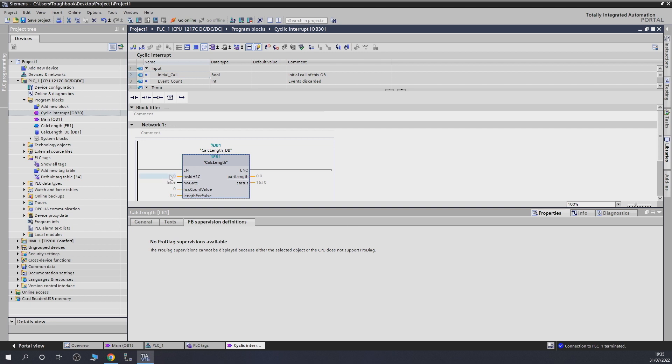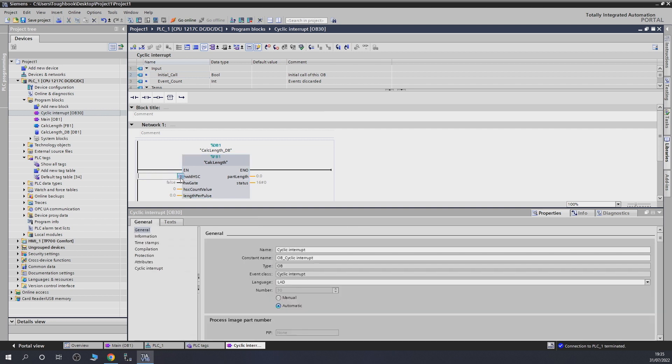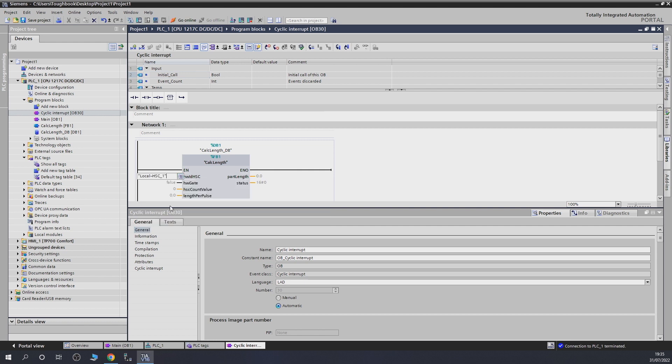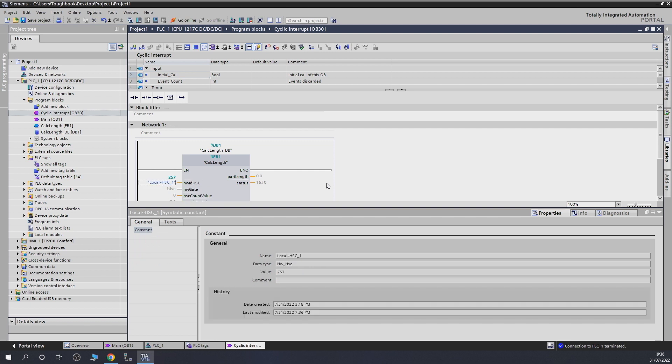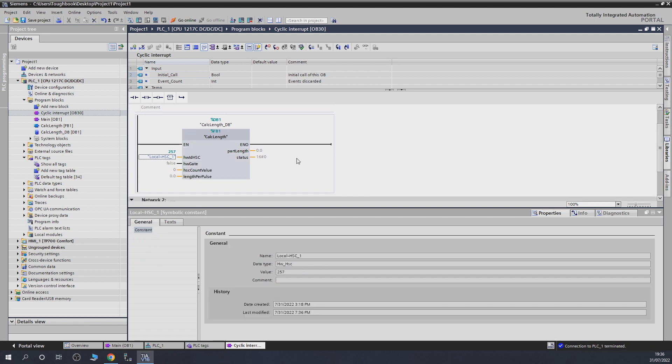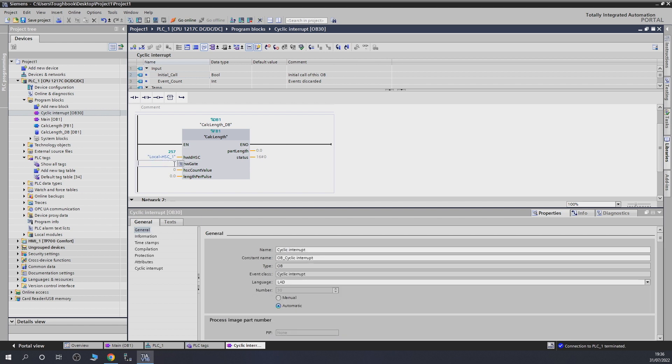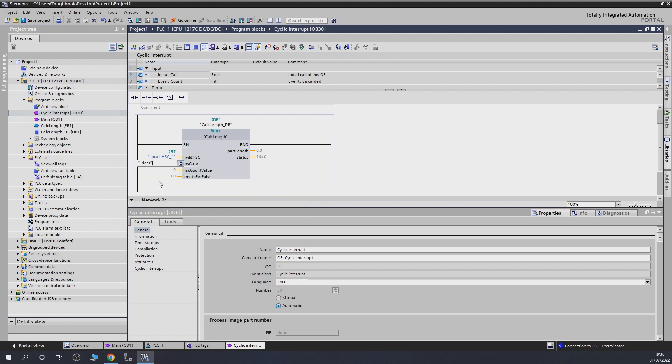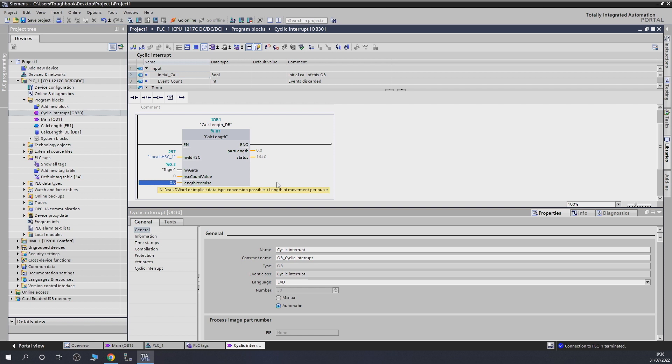From there on, we need to provide some values and data for this block. First one, let's give it which high speed counter is it. So, we're going to be saying that's going to be our high speed counter one. Having done that, the next one, we need to give him the gate. So, let's just remember our signal, which is going to tell the PLC to start measure, which is going to be called our trigger. I already prepared the flag for it, which is I0.3.